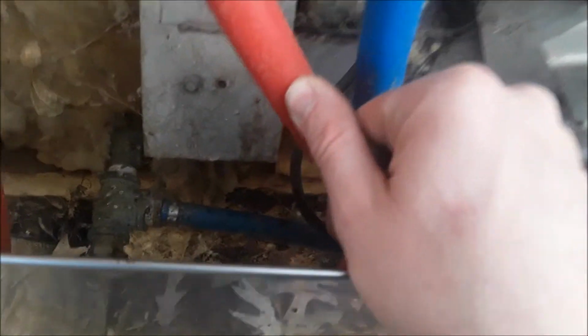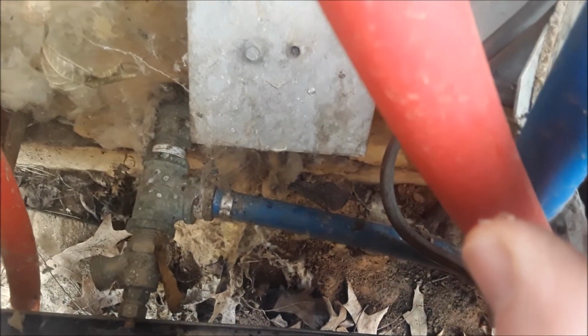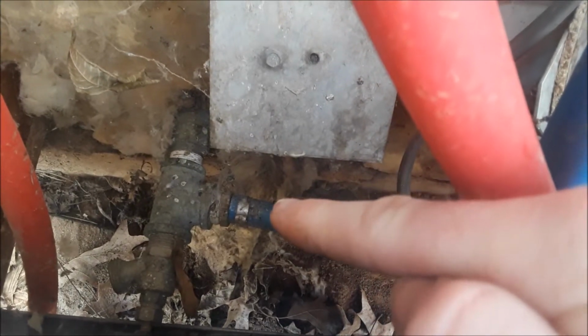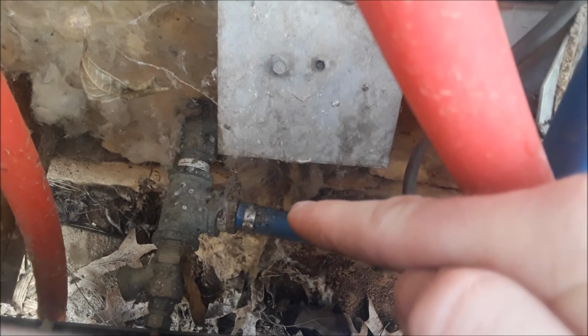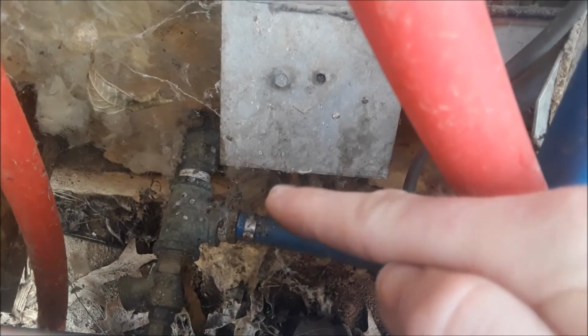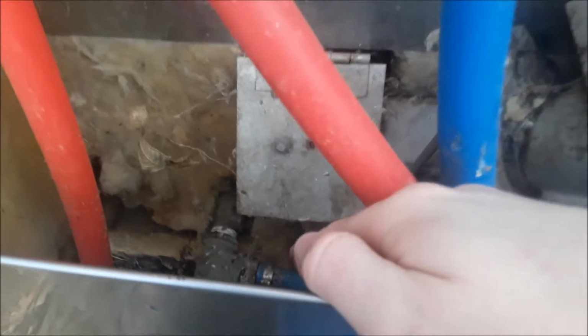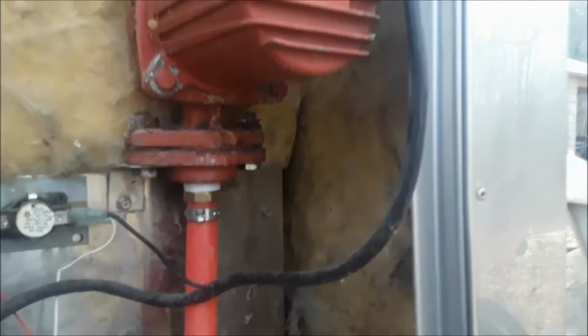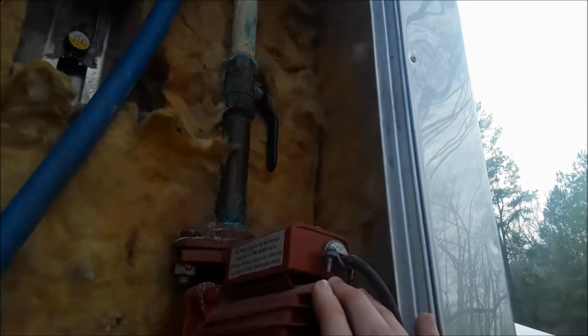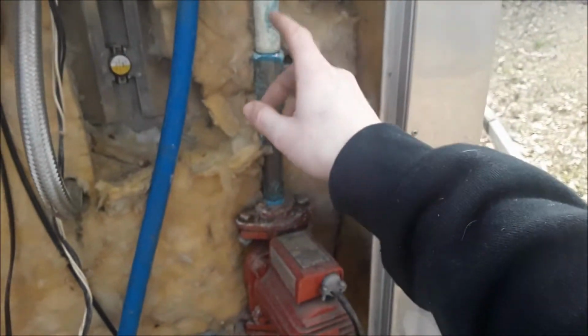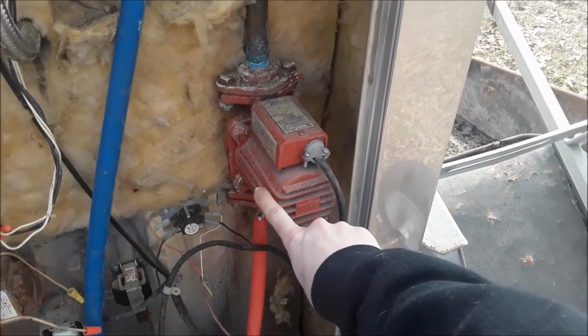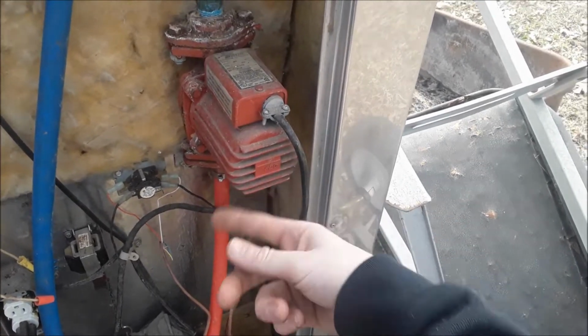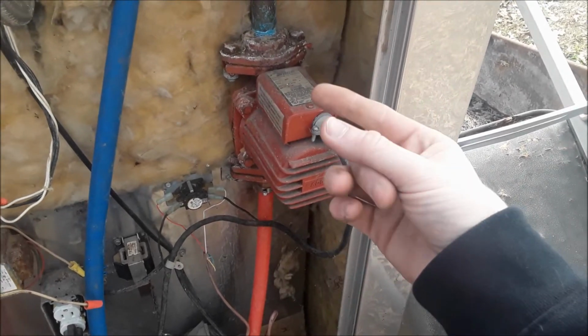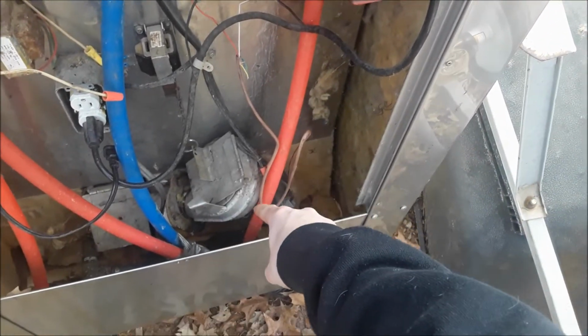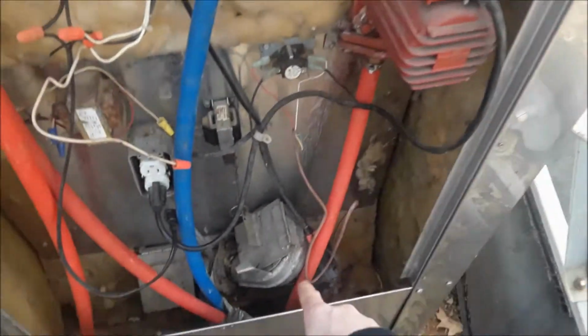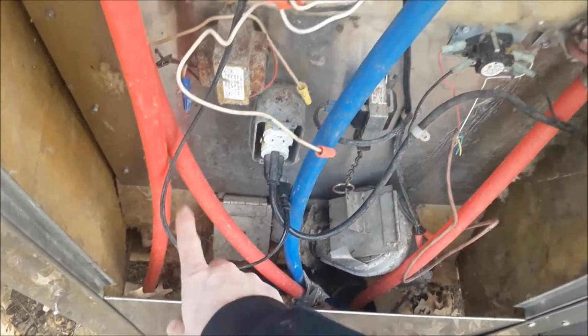It's blue, but it's not really like cold water from the house or anything. This is part of the heating side for my ductwork - the colder side of the radiator coming back to the heater with cooler water. The other side of that loop is this red, it goes to here, this is a water pump. So hot water in the heater gets circulated to the radiator in my ductwork with this pump. The pump kicks on when the house calls for heat, and it pushes the hot water underground to my house and then back through that bottom line down there to get reheated again.